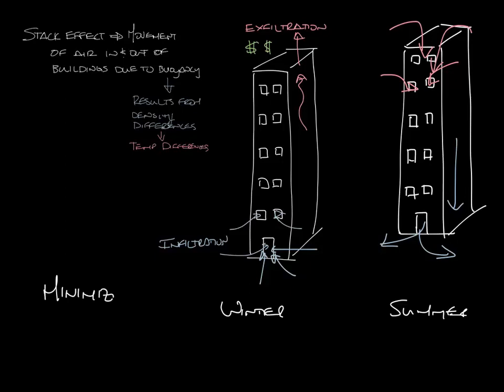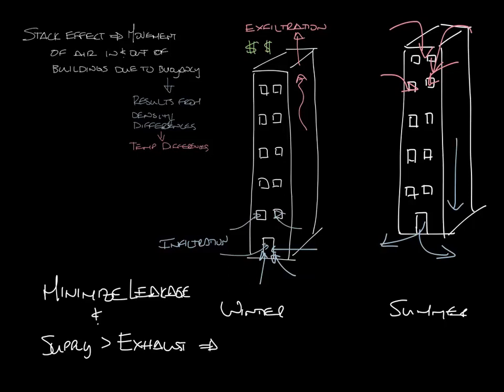To minimize stack effect, you should minimize air leakage in and out of a building, and also for most buildings you should supply more air into the building than you are exhausting from it, to keep it slightly positively pressurized.